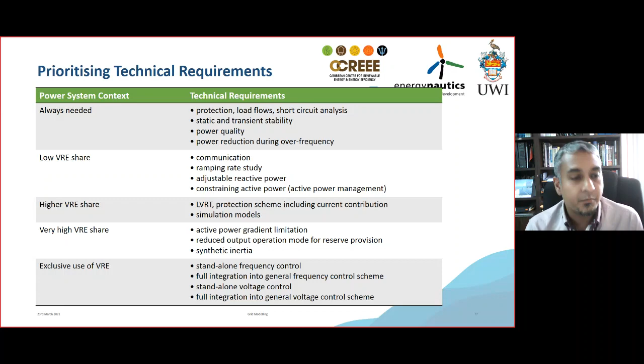Because what you now have is potential for energy and power, and depending on when you have a fault, you may need more power to ensure that you can supply this demand for a short period of time. That is a significantly different type of energy need, because your rate of response must be very, very fast, and therefore your customers must not see this outage. And this is against the backdrop that you do not have inertia on your system. The control system that generators normally have will give you some measure of inertia. You do not have that flexibility with the power electronic system. Therefore, you must have a very fast responding system, and your controls must ensure that you can respond faster than the mechanical actions of the traditional system.